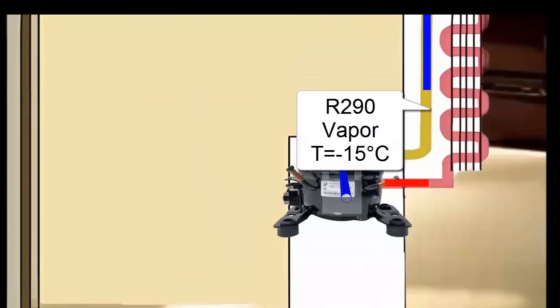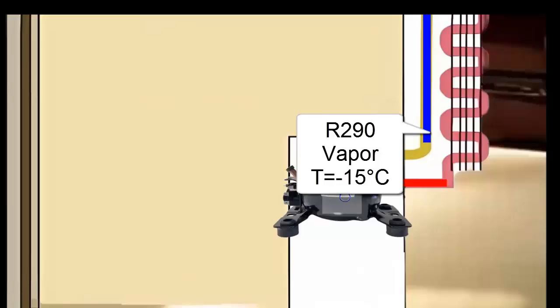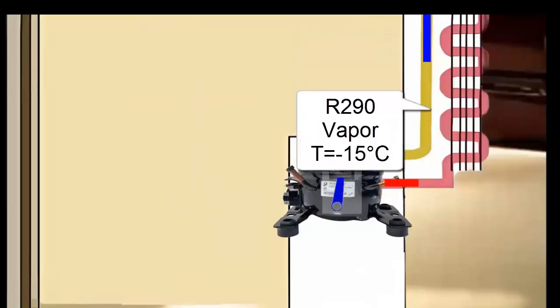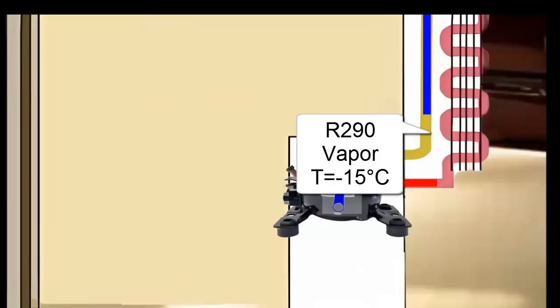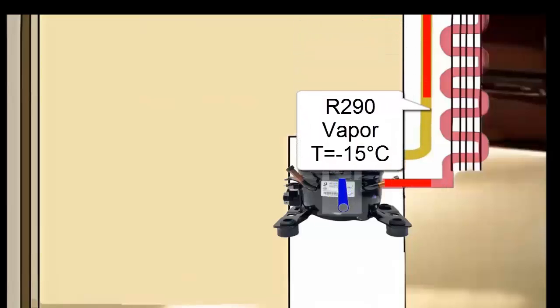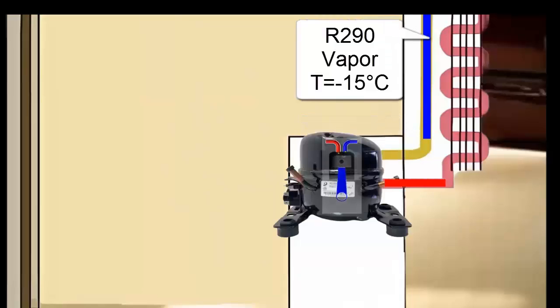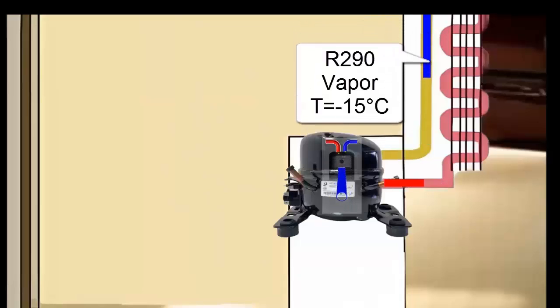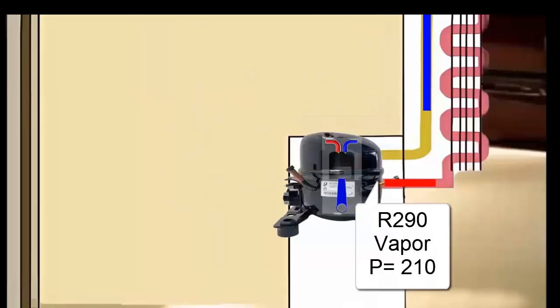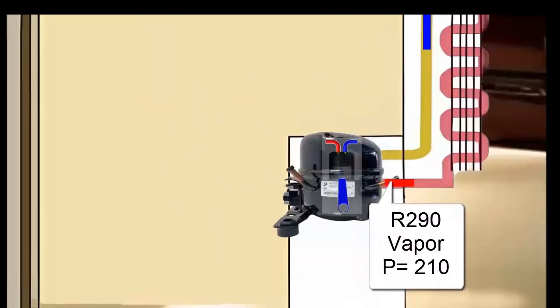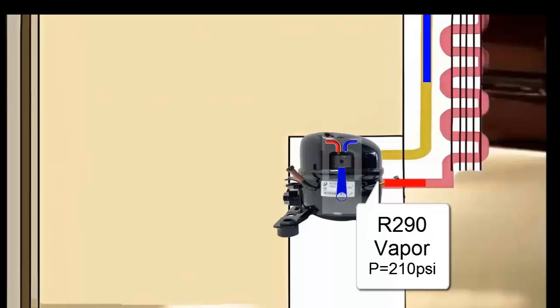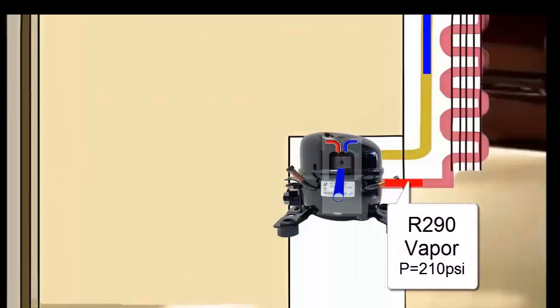The pressure and temperature of the R290 refrigerant increase significantly in the compressor. The pressure of the R290 at the compressor's exit reaches a value close to 210 pounds per square inch. The temperature of the R290 at the compressor's exit may be around 60 degrees Celsius.